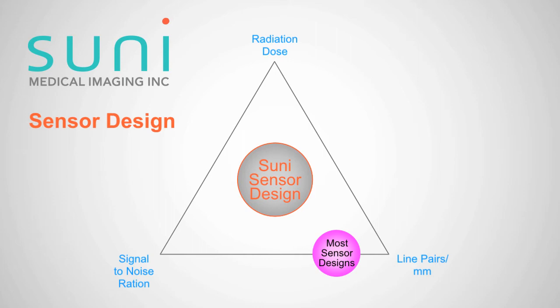The nowadays state-of-the-art digital sensors use a material called a scintillator to convert the x-ray image into a visible light signal, and that in turn is detected by the chip inside the sensor. The chip has pixels, much like a cell phone camera or a professional SLR camera, and pixels have many properties. For our discussion, the most important property is the size of the pixel — the surface area of the pixel.